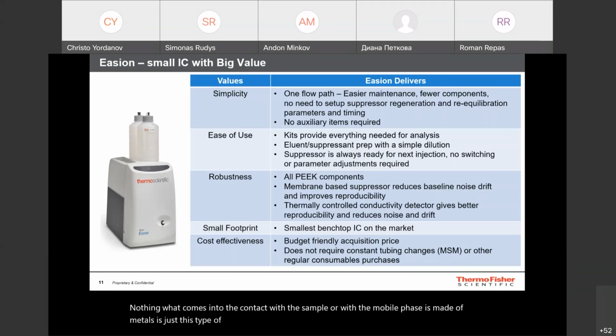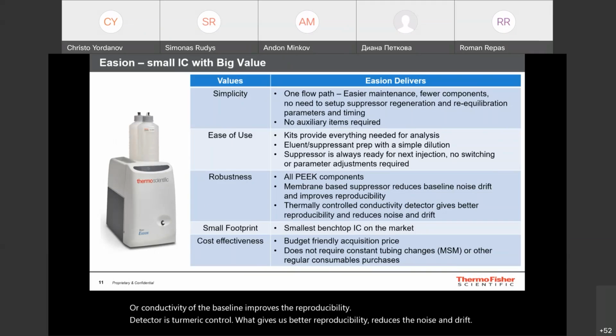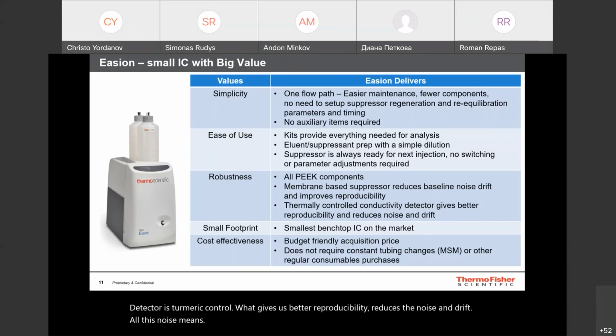So it's inert. Only one type of suppressor can be used here, and that's the chemical suppressor, which reduces the conductivity of the baseline and improves the reproducibility. The detector is thermally controlled, which gives us better reproducibility and reduces the noise and the drift. Less noise means better sensitivity, lower detection limits.